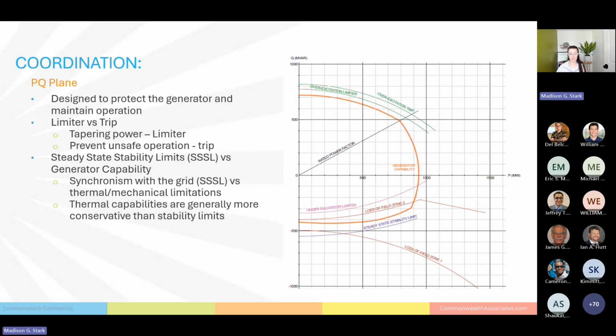And the reason why is this steady state stability limit here. Now, when you exceed the generator's thermal capabilities short term, the generator is probably going to be fine. It has the ability to sustain operation outside limits for a little bit. It's called thermal inertia. But with this steady state stability limit, breaking synchronization, the generator has no ability to withstand a deviation in that regard. If it becomes unsynchronized, that's going to cause instant damage to the generator and can be incredibly devastating. So that's why all of this is on the inner side of that, because we're trying to create a buffer with that steady state stability limit. What you see over here, these thermal capabilities are generally more conservative than the stability limits. It's that way on purpose. One of these is much more devastating than the other, so it's important to protect for the most devastating event.